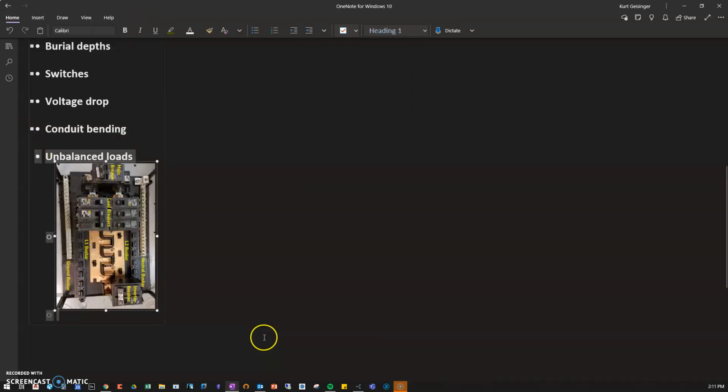And then finally, to sort of finish this thing out, your unbalanced loads. There's just a couple questions, and what I mean by that is, it's another way to say we have our neutral conductor. If circuit 1 has 6 amps, and circuit 3 has 5 amps on it, and they share a neutral, what is the load on my neutral? Well, it's the difference between the two.